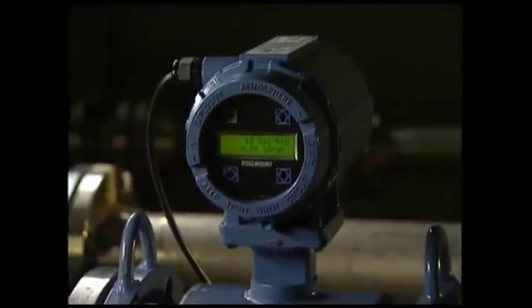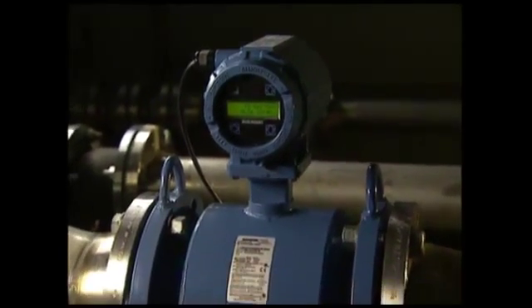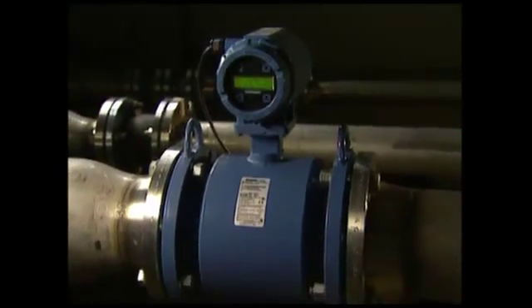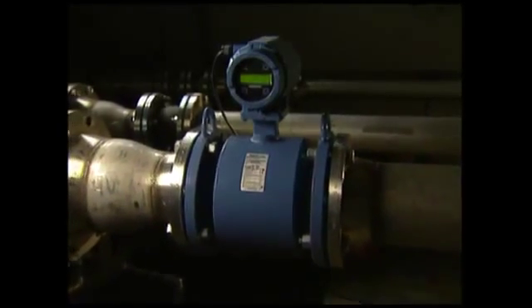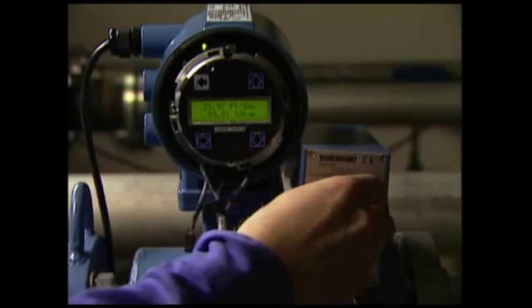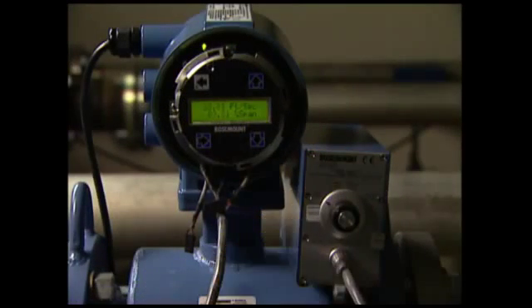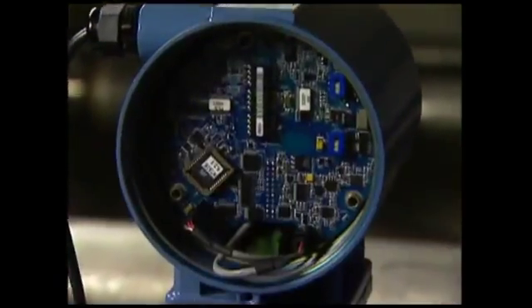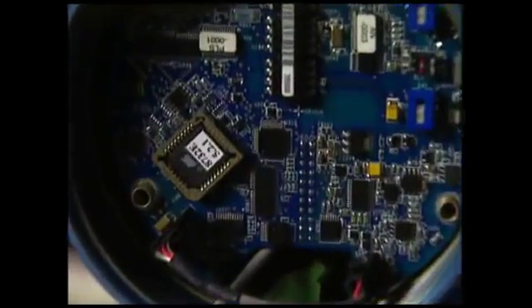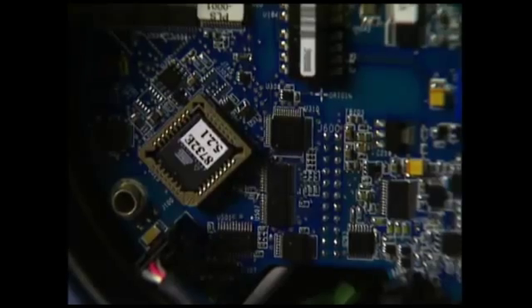It's important to note that Rosemount E-Series magnetic flow meters perform the 8714i diagnostic on both the transmitter and the flow tube sensor. In the past, external devices have been used to conduct these tests. But now, this same functionality has been built into the transmitter's electronics.